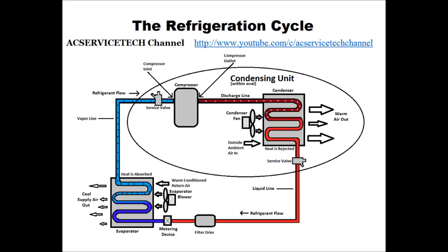So you have a low pressure, low temperature vapor coming into the compressor, and then high pressure, high temperature vapor coming out at its hottest point. Then it enters the condenser coil, where it starts to reject heat until it becomes a saturated state where vapor and liquid both exist. After that, it rejects more heat as a liquid. It's out of its saturated state, turns into a liquid, and continues to drop in temperature until it comes out past the valve. That is called the subcooling: the temperature decrease in liquid form.